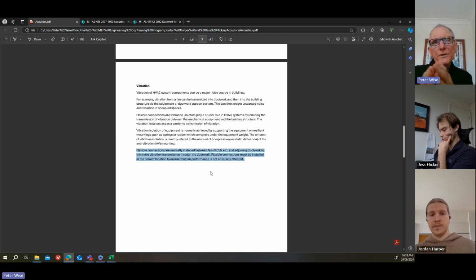So with an axial fan, you need to move the flexible connection back on the inlet side at least, past the transition or the first piece of duct, put it back there so that any disturbance of the air straightens out again before it enters the fan. If you look in the Fantech catalogue, there's a section on fan do's and don'ts.